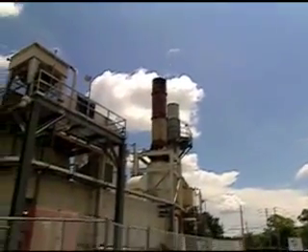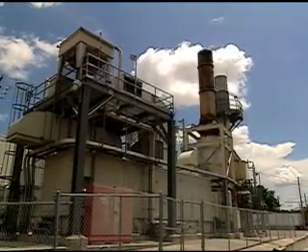In the plant, we're gradually replacing older fixtures with high-output fluorescent fixtures that consume just about half the energy. We've also reduced our natural gas consumption by 25% in the plant. In fact, we generate about 75% of our in-season power needs and almost 100% of our off-season needs through an internal system. With the installation of on-site cogenerators, we now burn natural gas to generate both electricity and steam. Previously, our boilers were powered by oil. Natural gas is cleaner, and with one burn, we fill two needs, electricity and steam.